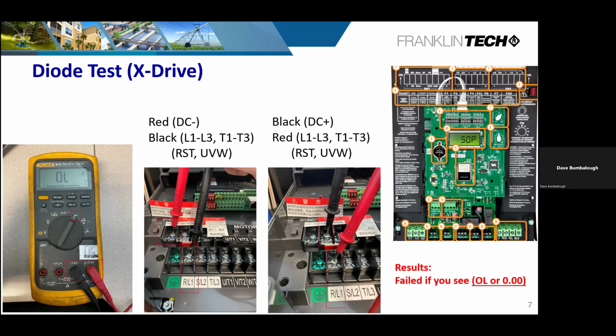Now, if it's on both sides, in my personal opinion, chances are it came in on the power side while the unit was running and went through the system and zapped both sides, like some kind of electrical surge or spike or transient or even a lightning storm. As we get through this, the question always comes up, how do I identify what's been damaged on the output side? You know, the input side is pretty obvious, the output side, not so obvious. So we make a meter for that.